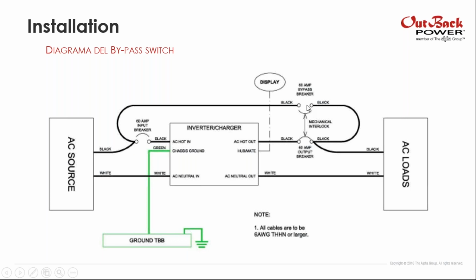If this breaker, the 60 amp bypass breaker, is closed, then this breaker, the 60 amp breaker for the output, will be open. So the energy will flow like this, directly to the AC loads. What happens if I want to use the AC output? Then the 60 amp output breaker is closed, and the 60 amp bypass breaker will be open. So those cannot be open at the same time or closed at the same time. That's how the bypass switch works. Great, don't you think?